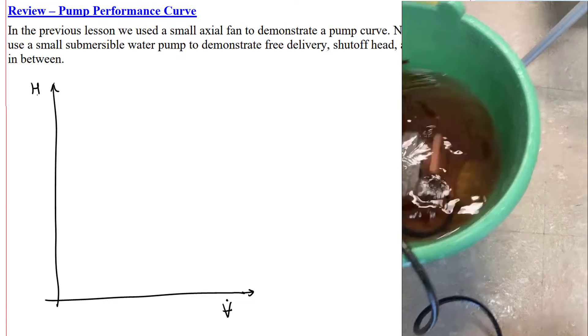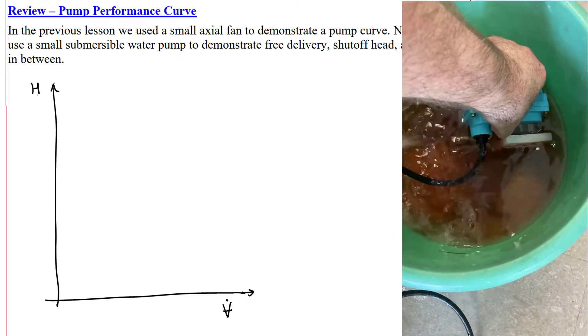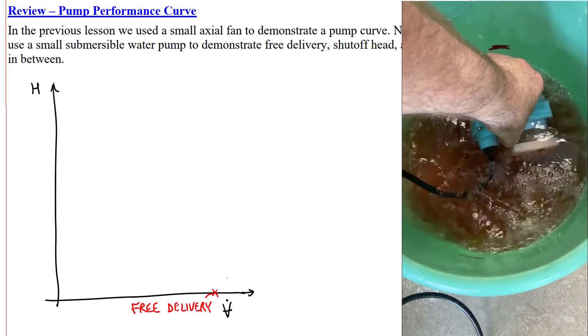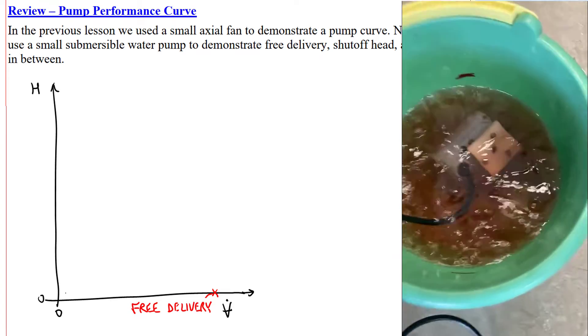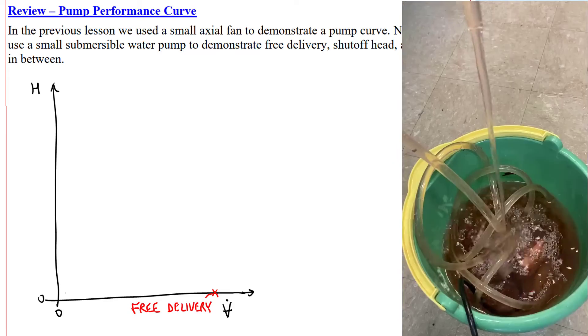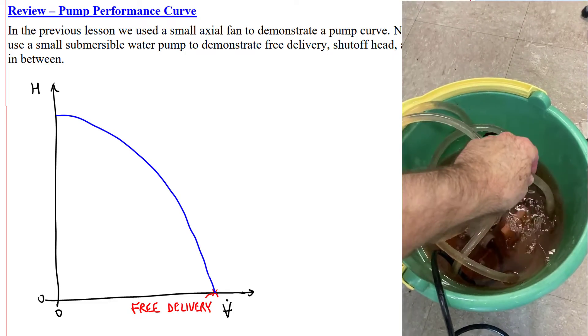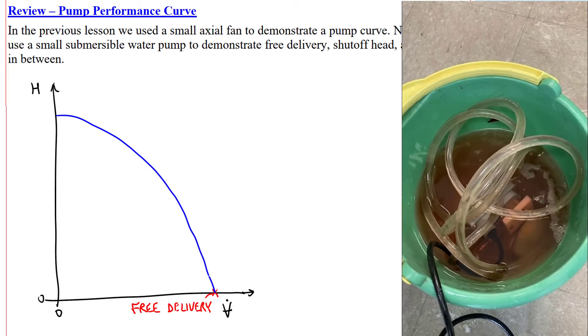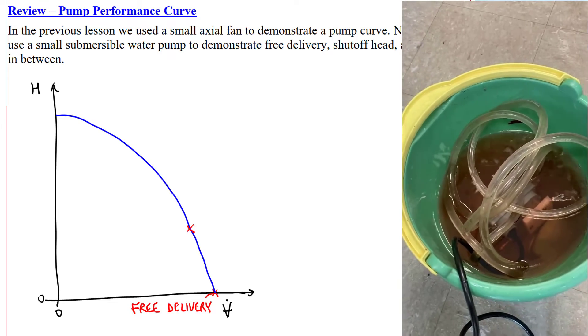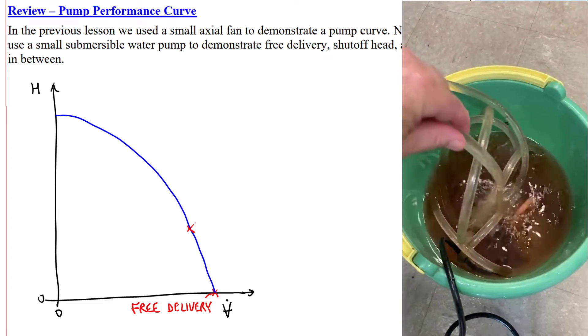When we turn on the pump, the flow rate is at its maximum. This is what we call the free delivery, which is the maximum volume flow rate that the pump can deliver, and it occurs when there's zero head. Here's a typical pump performance curve. However, we attach a flexible tube to the hose barb at the outlet. Now there is a head loss, but the volume flow rate will be lower. We're operating somewhere here.